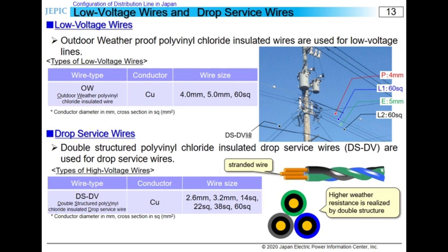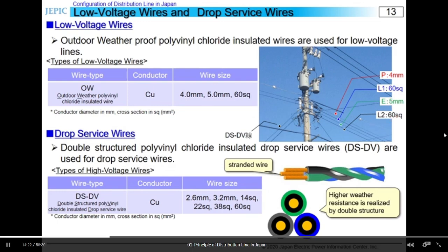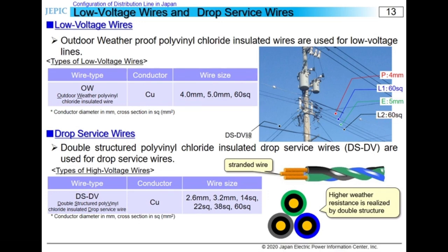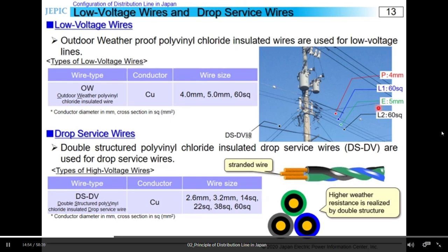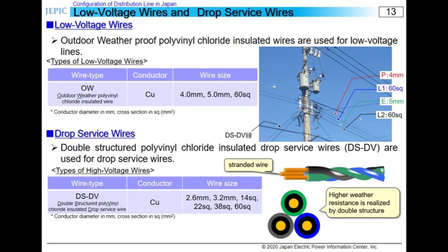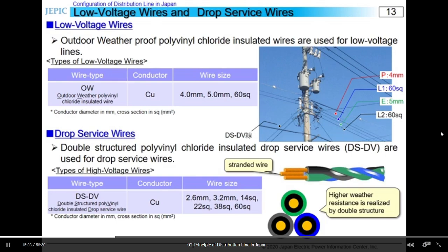In this picture, the order of the low voltage line is the same as the connection figure in the previous page. The lines L1, L2 are usually the thickest. This is because the current of both single-phase and three-phase flow through L1 and L2 lines. Vice versa, P line is usually thinner than L1 and L2 because only three-phase currents flow. E line is normally one size smaller than L1 and L2 as long as voltage drop doesn't matter. And also, if only E line gets disconnected, over voltage might be supplied to lighting load customers, so it's located between other lines so that only E line doesn't get disconnected.